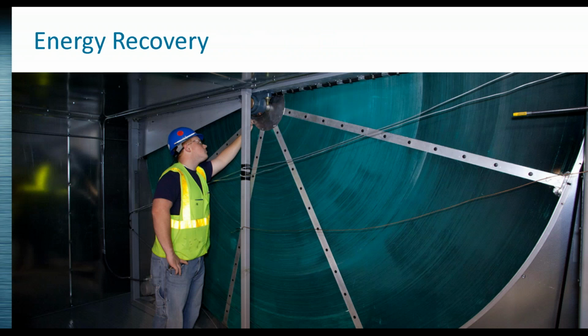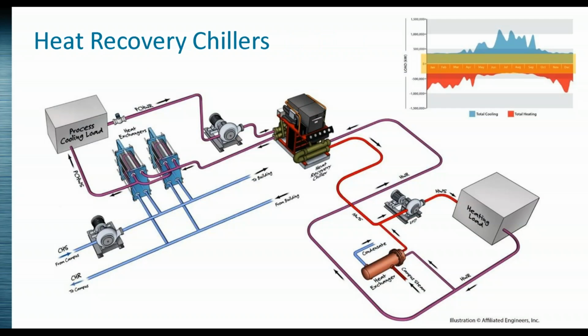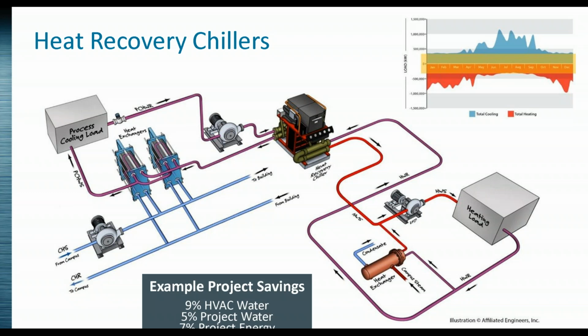From an energy recovery perspective, wheels continue to be prevalent in the market, but we're seeing more advanced runaround loop systems coming into play, making big strides. We see heat recovery chillers, the modular type that take advantage of the simultaneous heating and cooling loads that persist in laboratory facilities, providing equipment that—instead of rejecting heat via a cooling tower—takes that heat, bumps up the temperature a bit, and uses it in the building. That's a great example of the energy-water nexus, where you get HVAC water savings.